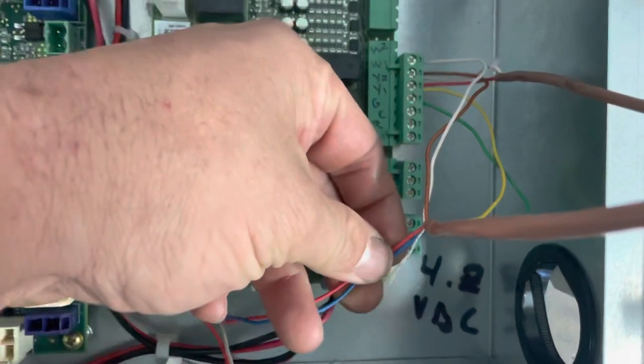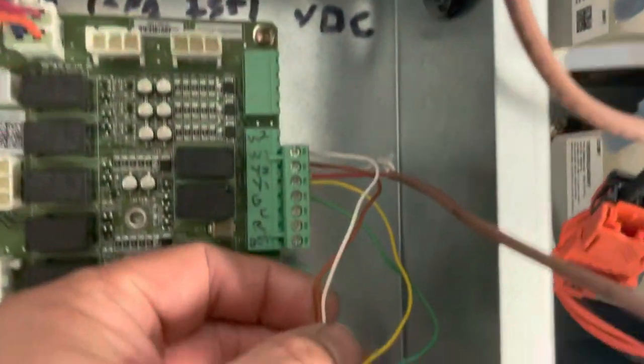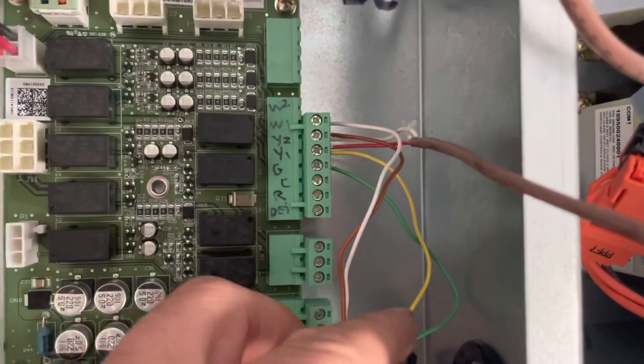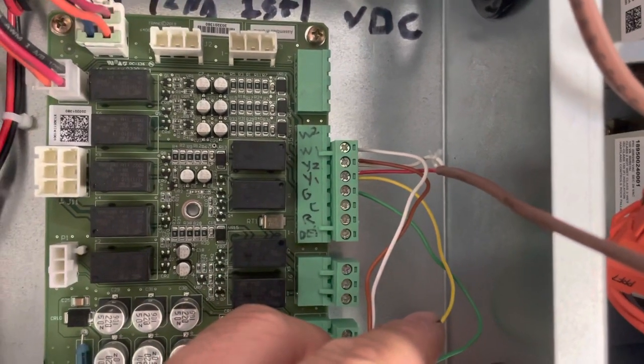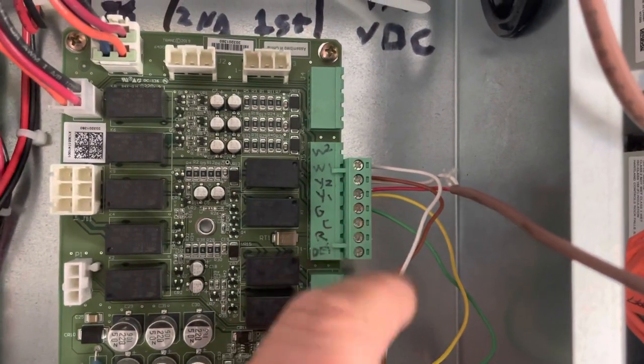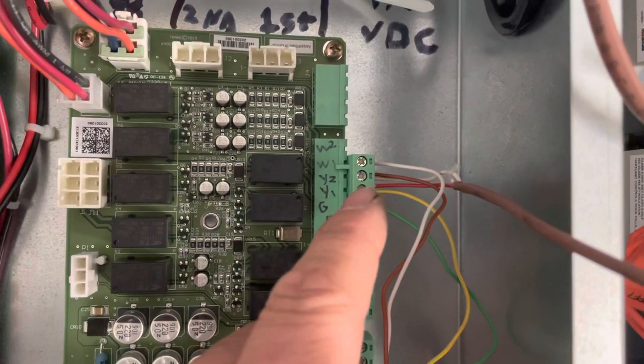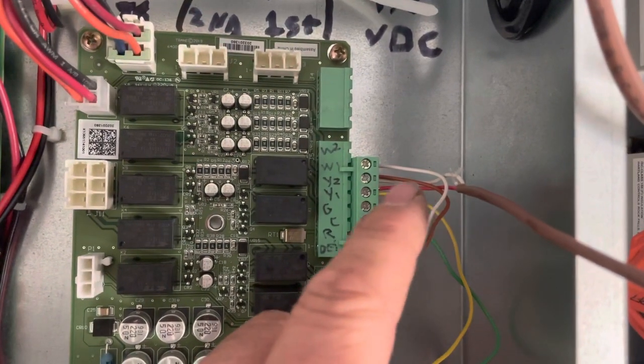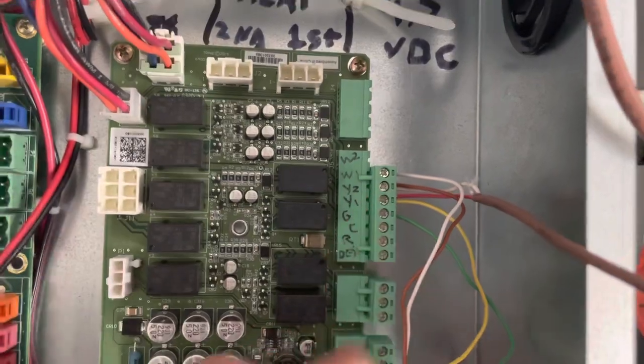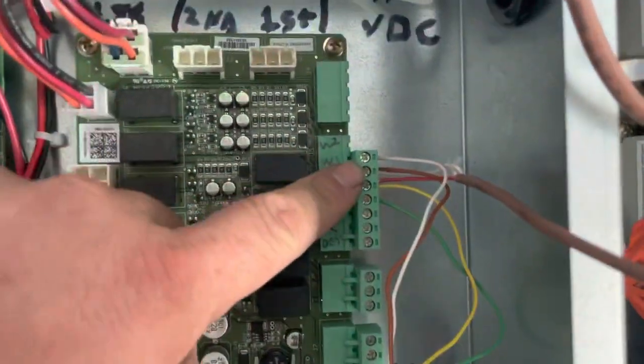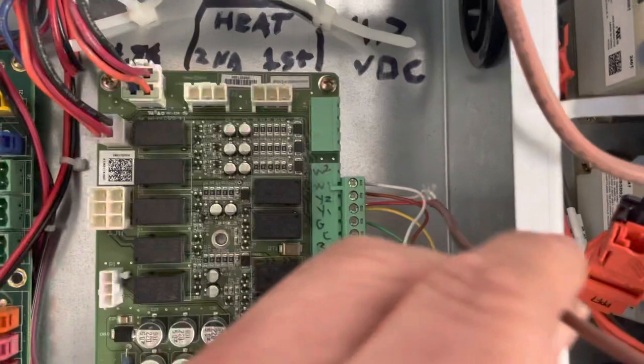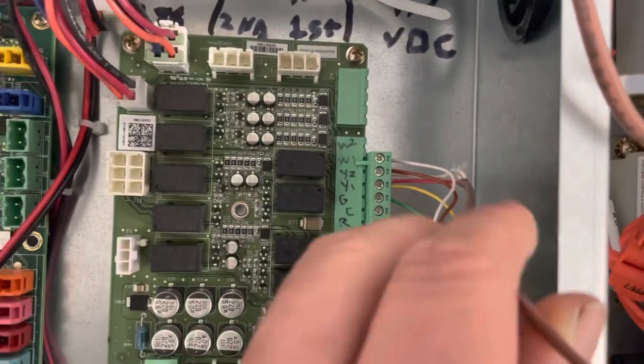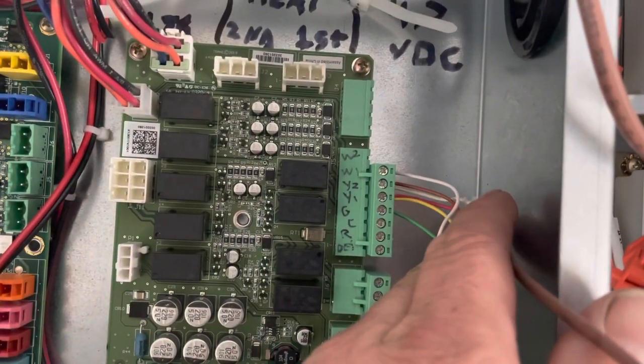If you look at my power and my common connected, my other wires: I have my green for my blower going to G, yellow is going to Y1, brown if you follow that one's going to Y2, and then white is going to be for my W1 in this case. And then back here behind it are my two wires that I'm using for this bundle. So that's my two wire going to my outdoor unit, again it's just connected to Y1 and Y2.